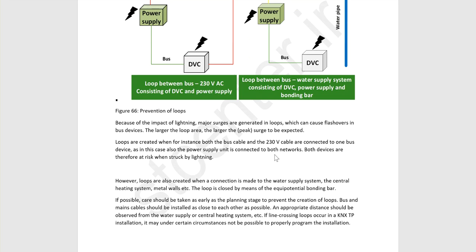The central heating system, metal walls, the loop is closed by means of the equipotential bar. If possible, care should be taken as early as the planning stage to prevent the creation of loops. Bus and main cables should be installed as close to each other as possible. Remember that bus and main cables should be installed as close to each other as possible. An appropriate distance should be observed from the water supply or central heating system.